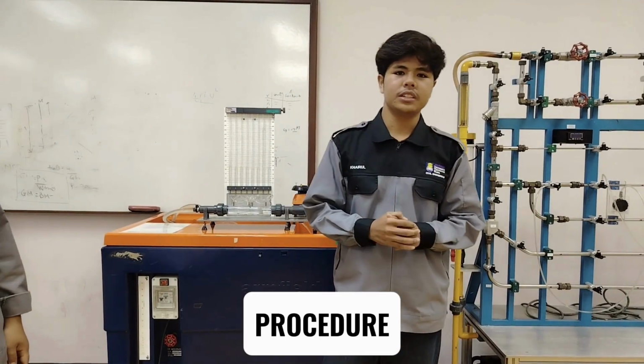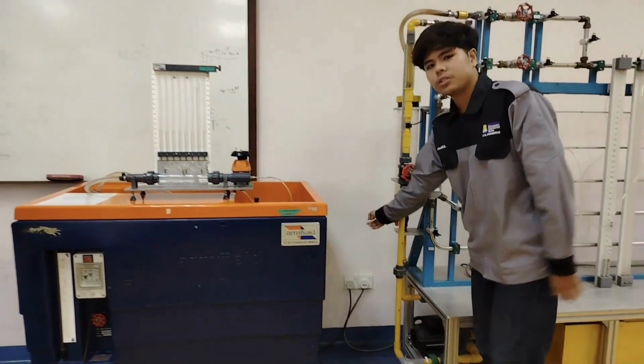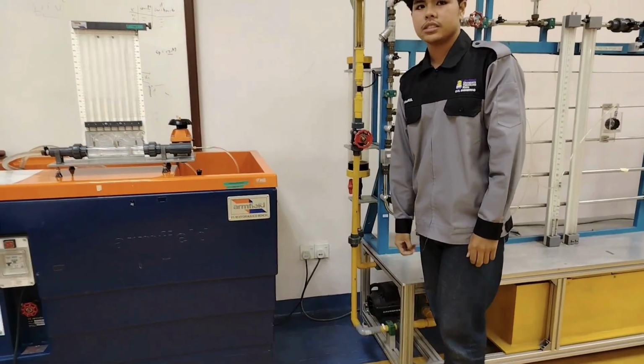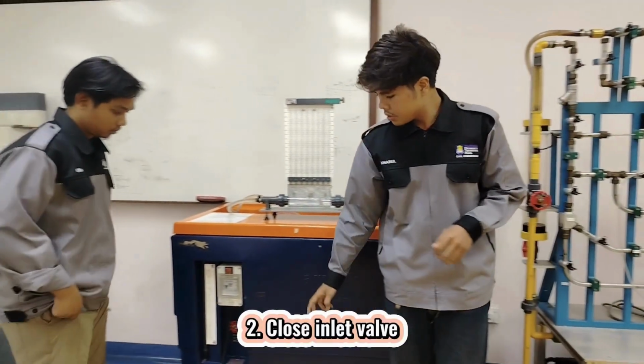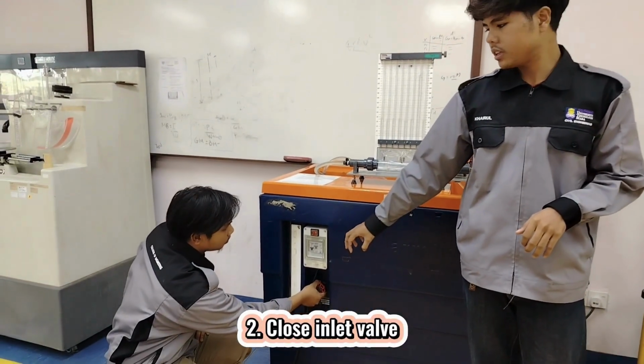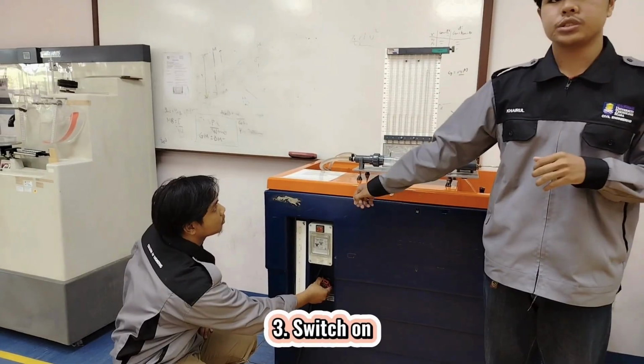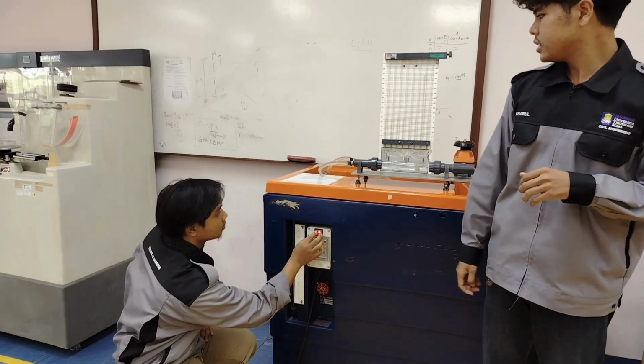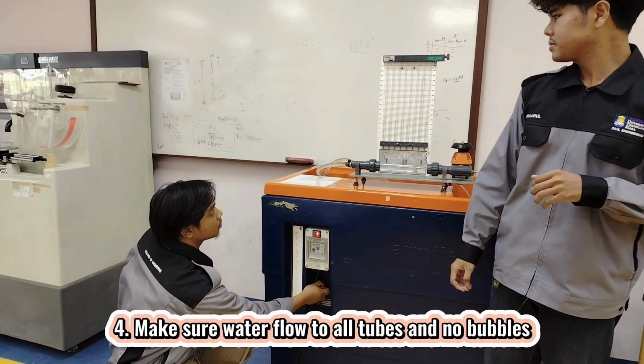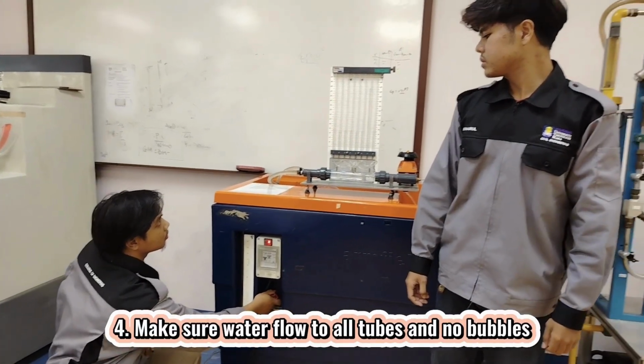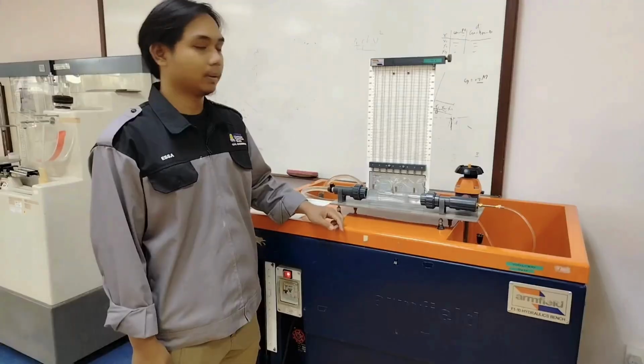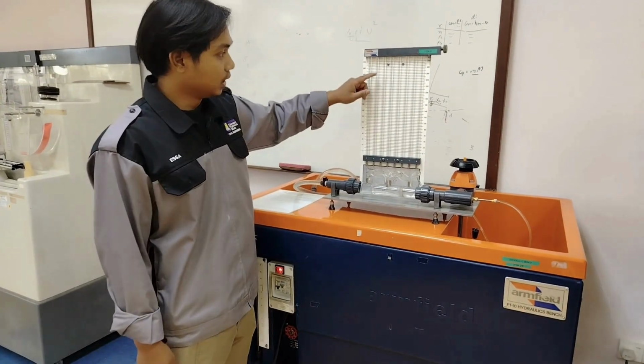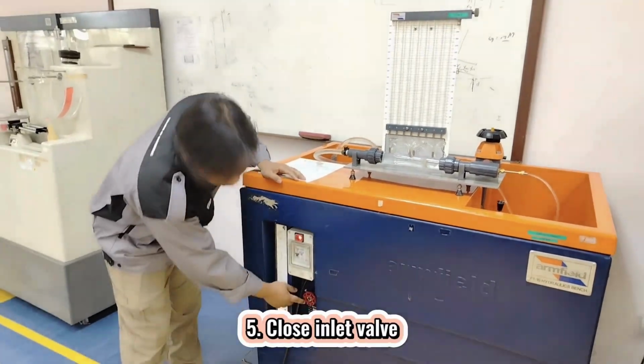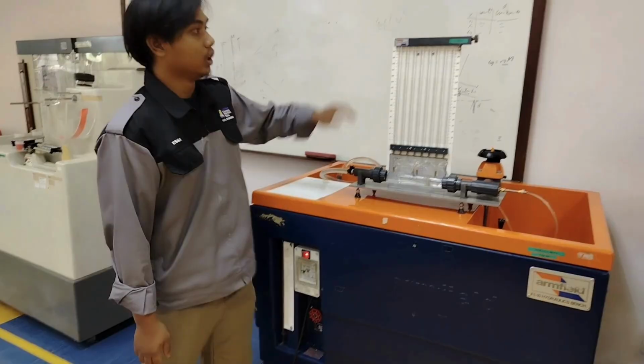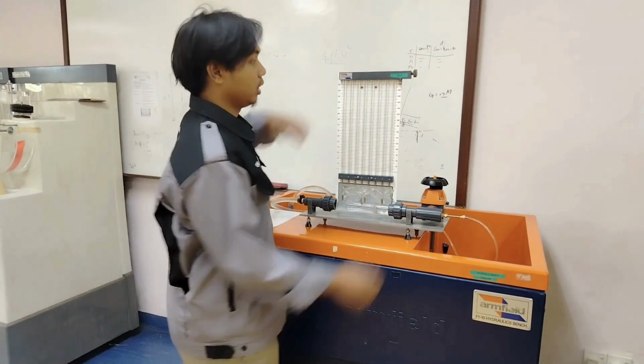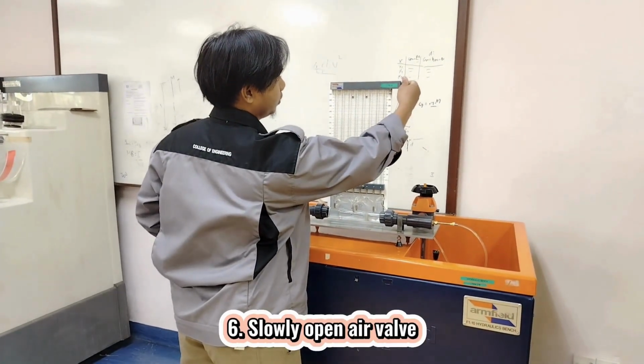To begin the procedure, firstly, we must switch on the main switch. Second, we need to close the inlet valve, and then we open the switch. Then we need to wait. When all the bubbles disappear, we close the valve and then we open this valve.